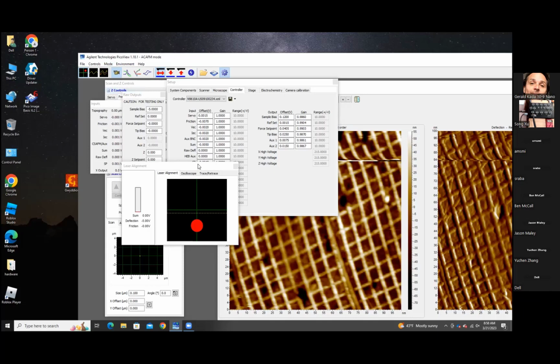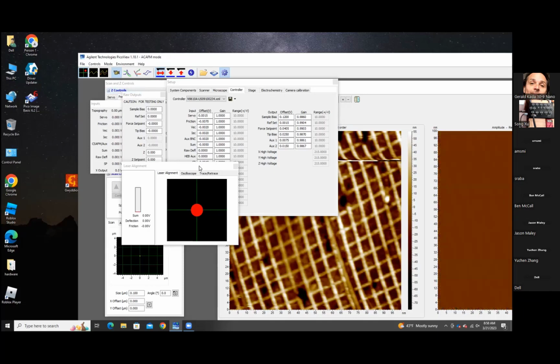ACAFM. Okay, now the yellow dot line disappears. This is also a reminder that we're actually not in contact mode, we're in AC mode. So when you see the dotted line, when you align your detector, your PSPD, you always align it so that the red dot is slightly below the center line. When you go to contact, it goes to this. When you go to non-contact, this dotted line disappears.